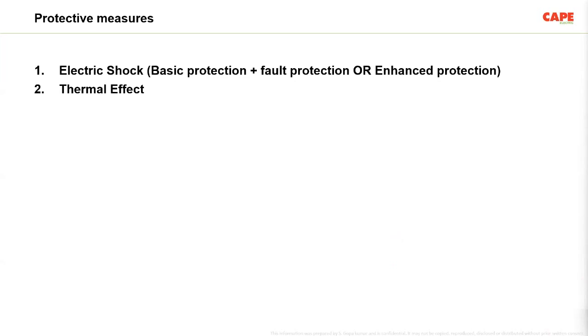The thermal effect protection is achieved by avoiding heat accumulation, heat radiation, and hot elements in an electrical installation. Then you have to have temperature limits, you have to have seals of cable penetration, and you have to limit the temporary over voltages, you have to limit the lightning surges, and so on. So a combination of protective measures is required for thermal effect. Also, a combination of protective measures is required for overcurrent. Whenever in the standards or technical books it is written as overcurrent, you should think that it is an overload current or a short circuit current. Both together are called overcurrent.